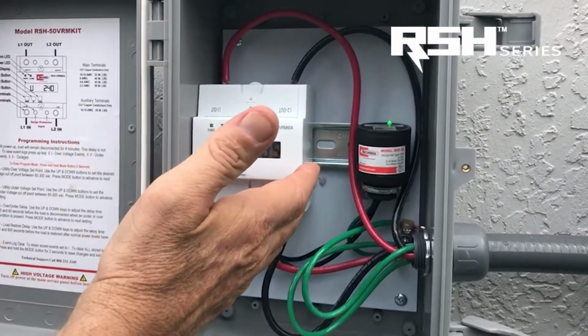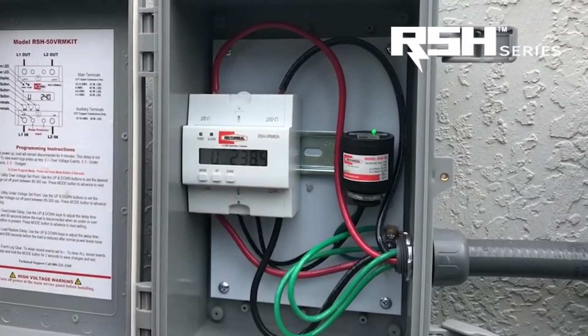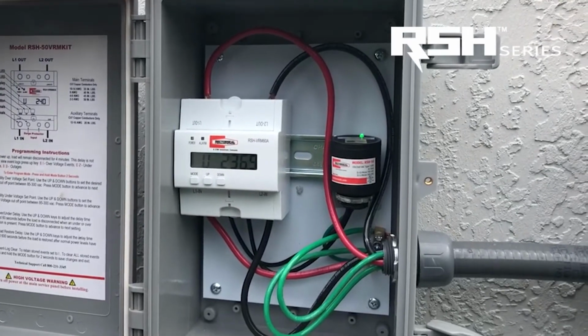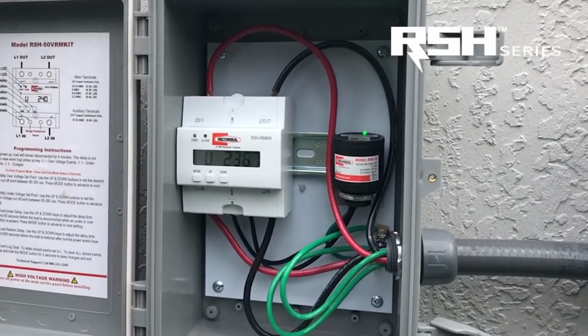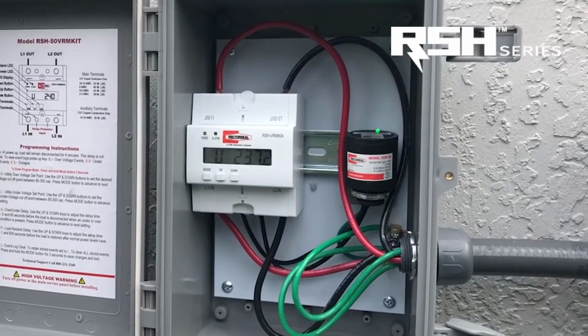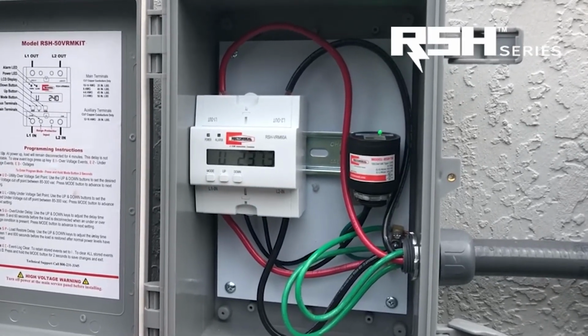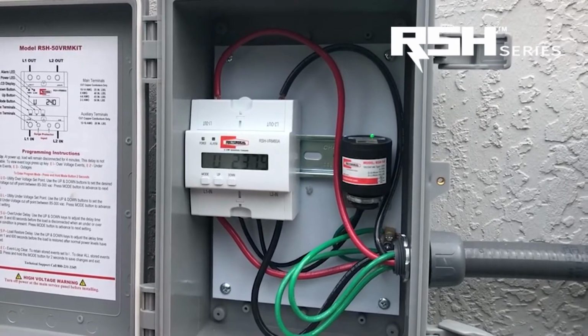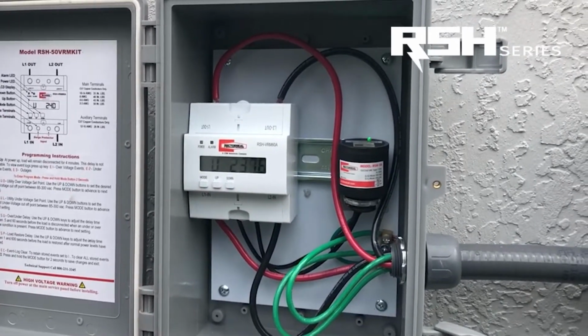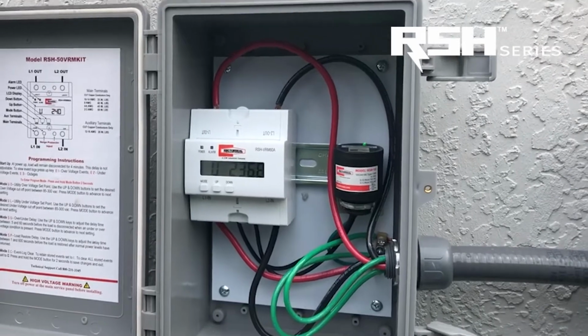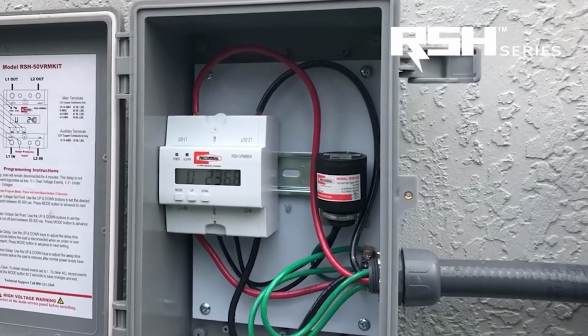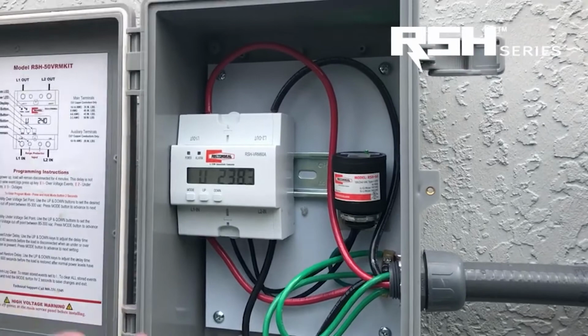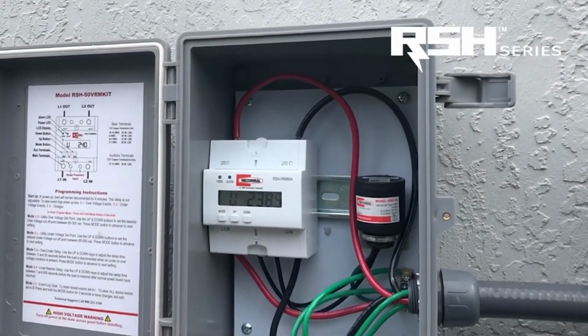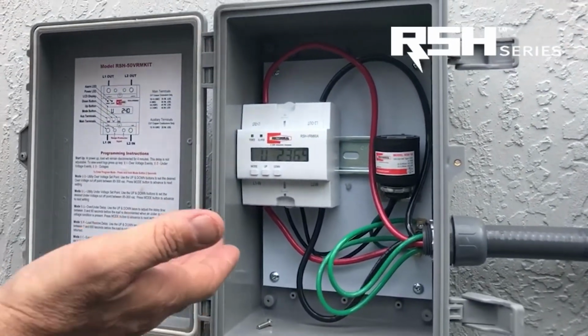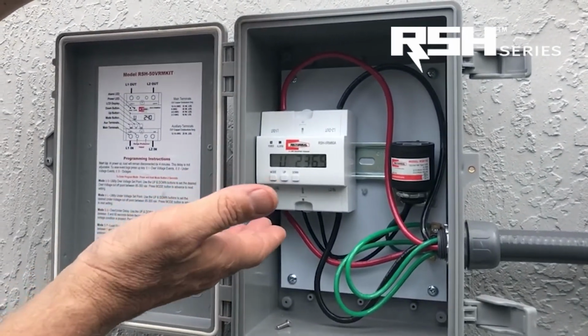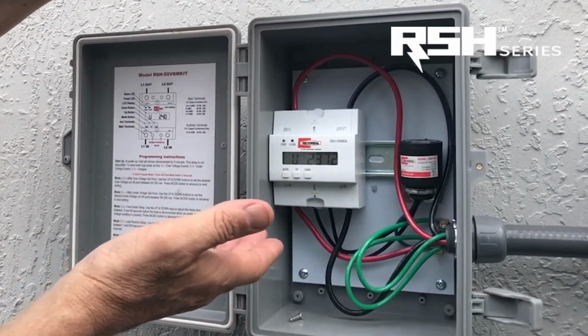So what we want to do with this device is program it so it shuts off when the electrical system hits a high power threshold and a low power threshold, which is also known as brownouts. When the power goes above 240 volts, it can reach a dangerous level that can damage electronic circuit boards and electronic components. When the power dips low, it can burn out motors. So there's a safe window to operate within, and this unit will allow you to program that window.